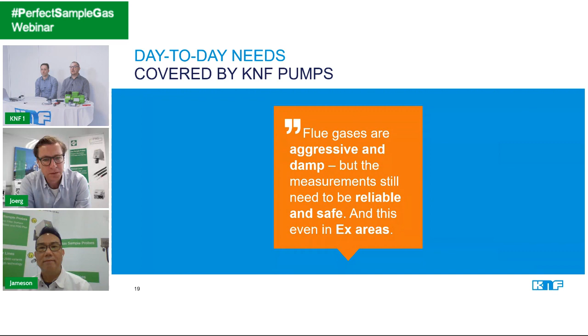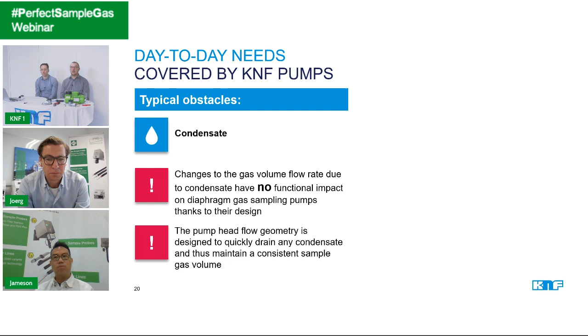The next topic is condensate, and how to handle condensate in the pump, or whether condensate is an issue for the pump. Here we want to clear up the misconception that diaphragm pumps cannot handle condensate - that's absolutely not true. Of course, condensate in the pump has some effects on performance, maybe some pressure or flow rate changes, but it has no functional impact. We do not expect the pump to get destroyed or fail early because of condensate. We have no disadvantages here compared to other common pump principles in the market.